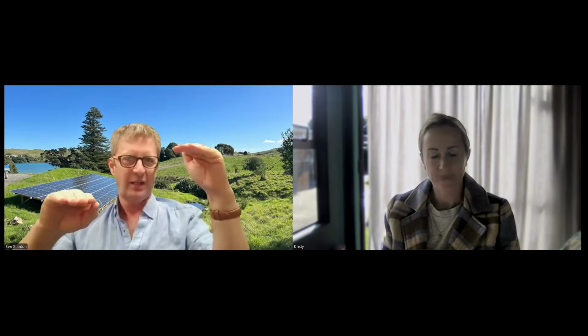Correct. So in some cases on the grid at the moment, the lines company or the network company is tapping those transformers high to handle extra load on their network. In some cases where they upgrade a transformer, they will just arbitrarily tap it at 244 volts. So you can see when you get a system that has data coming off it every 5 minutes or so, even at night time, in the middle of the night, that voltage is up at 244 volts. Then during peak times it drops down to maybe 240 or 235 when everyone's using everything, and then it jumps back up again.